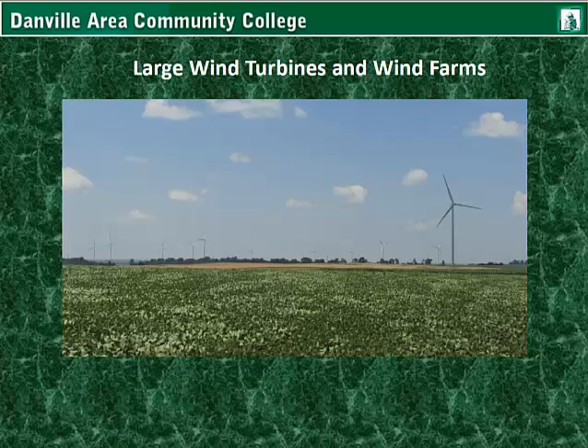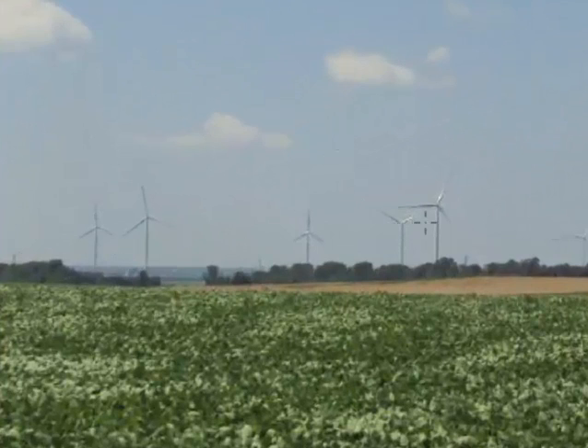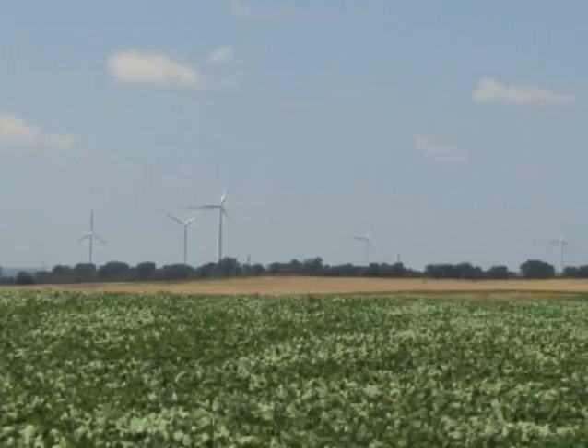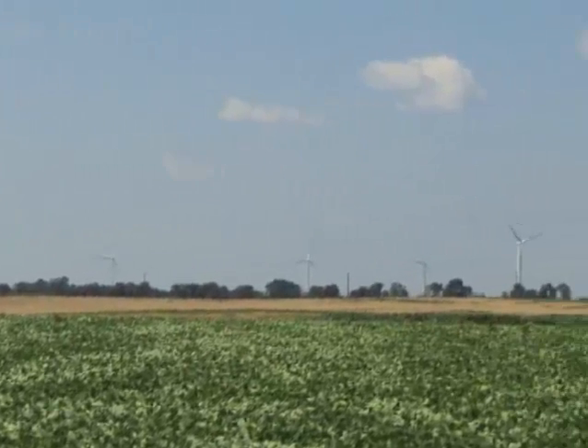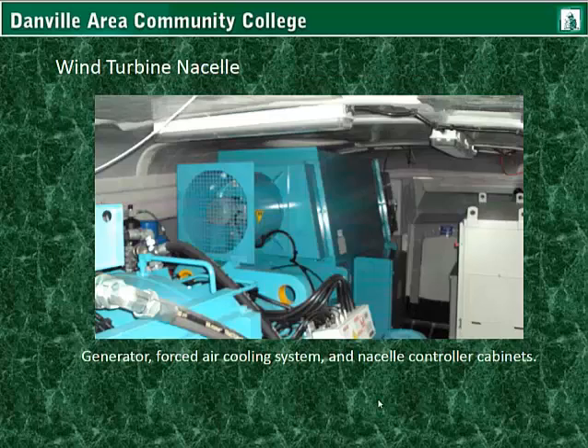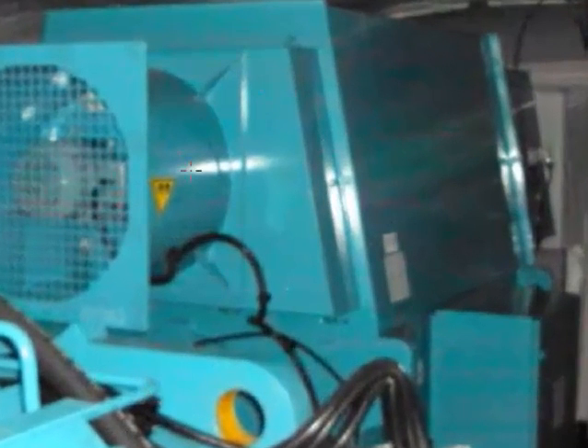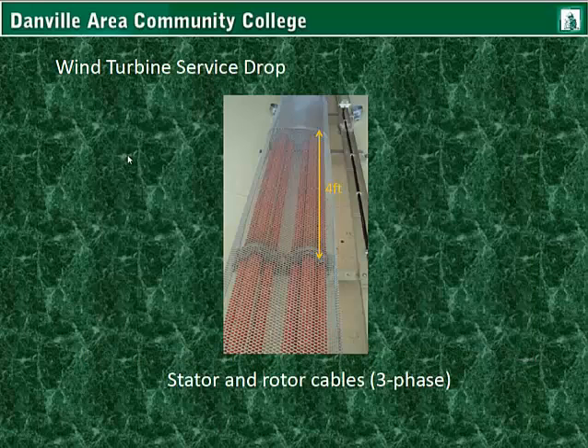Getting away from the grid and residential systems, let's go into the large wind turbines and their systems. An IPP has contracted the installation and connections of these towers, and they monitor their output into the grid. These large systems are called wind farms because they are harnessing or farming the wind for energy production. The wind turbine nacelle houses the generator, gearboxes, and other components, including a forced air cooling system and nacelle control cabinets. From the generator, there are stator and rotor cables — three-phase AC — and they go down the tower to the base.